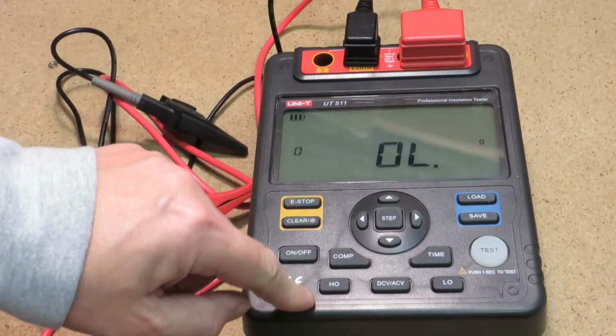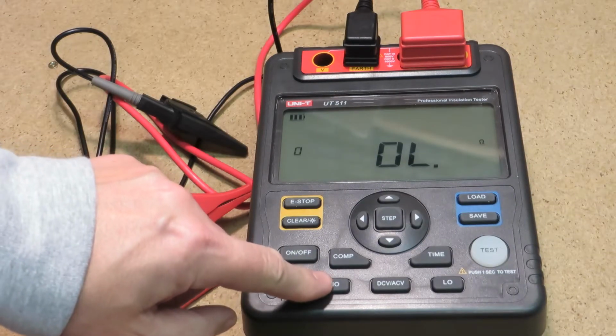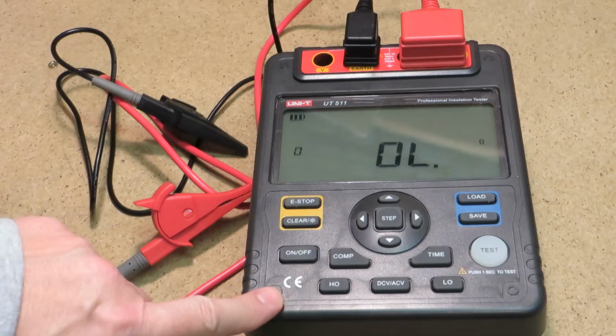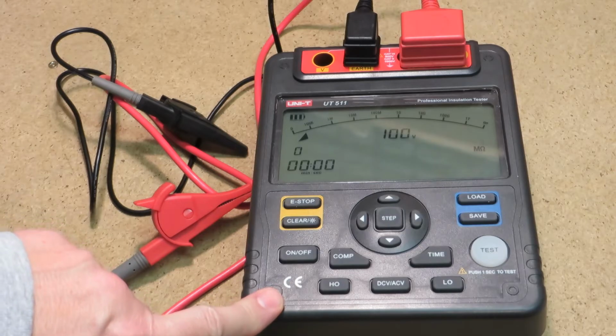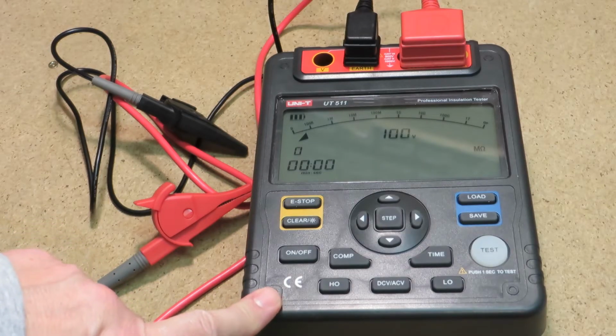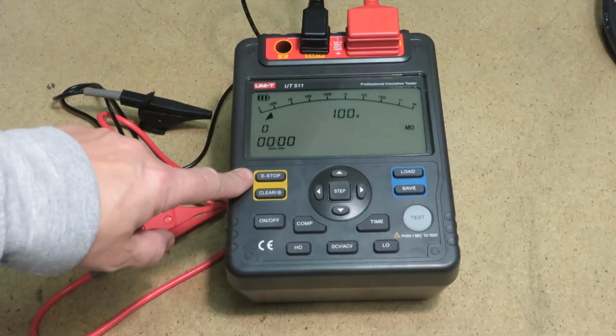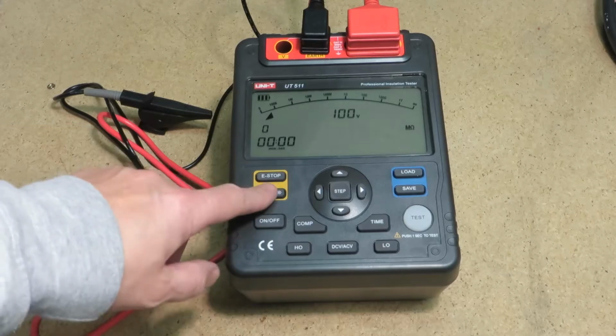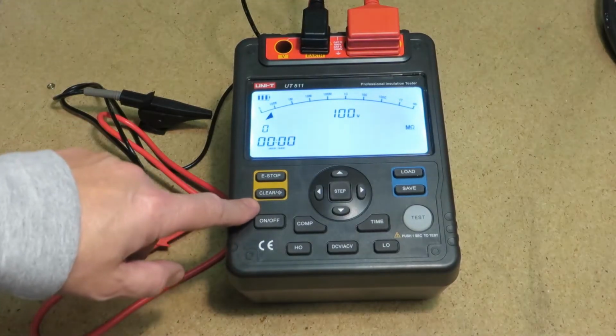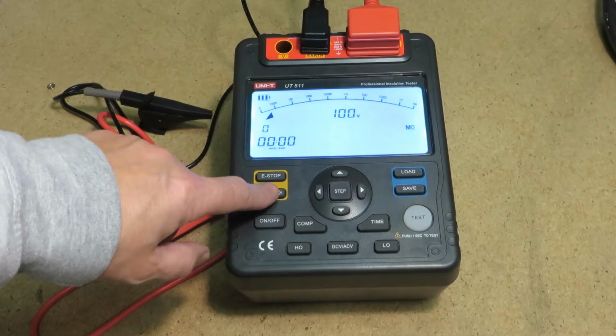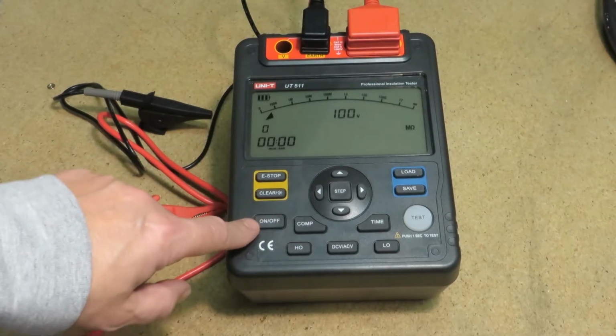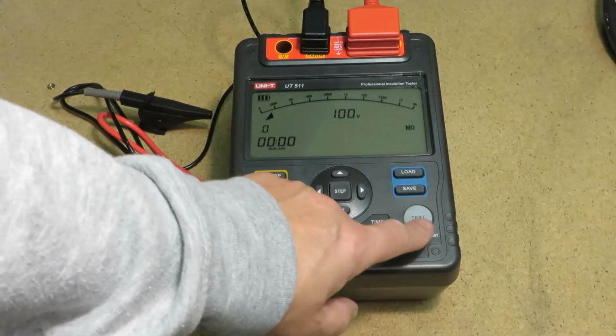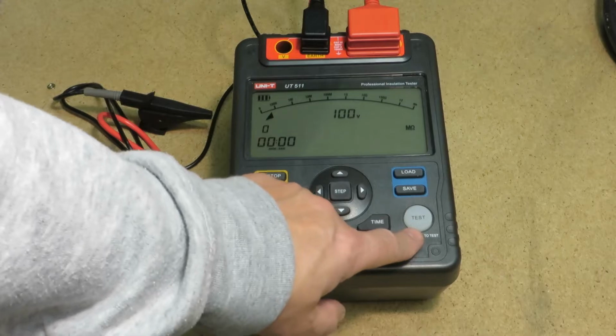Now let's come to the main application by pressing HO for initiating the insulation resistance measurement mode. With the emergency stop button, you can switch off the meter immediately or shut down the meter when it crashes or doesn't react anymore. Pressing clear will erase the memory, or by long pressing switches on and off the backlight of the display. Long pressing the test button will start the insulation measurement.